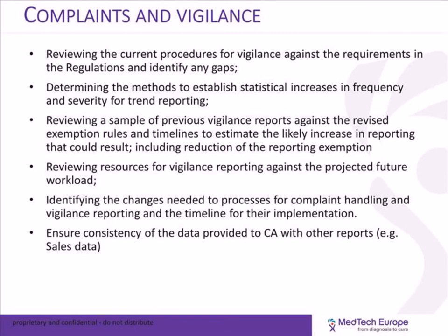We need to identify the changes that need to be processed in the complaint handling and the timeline for their implementation. This is important, and to ensure consistency of the data provided to the competent authority with the other reports. Some of this information will be in, say for example, the PSUR, and we need to make sure that the data are compatible, coordinated, and in synchrony, because discrepancy between the data may lead to further questions from the authority.